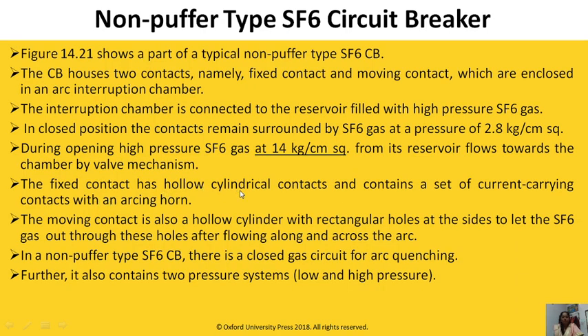The fixed contact has a hollow cylinder design and contains a set of current-carrying contacts with an arcing horn. The moving contact is also a hollow cylinder with rectangular holes at the sides to let the SF6 gas out through these holes after flowing along and across the arc. In the non-puffer type SF6 circuit breaker there is a closed gas circuit for arc quenching. It also contains two pressure systems: low pressure at 2.8 kg/cm² and high pressure at 14 kg/cm².